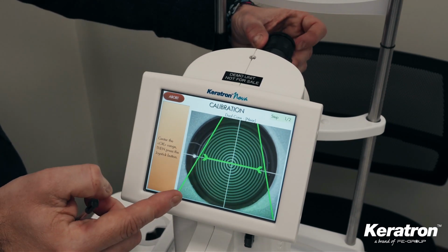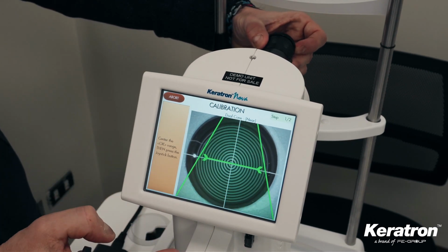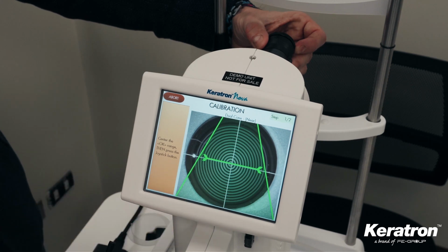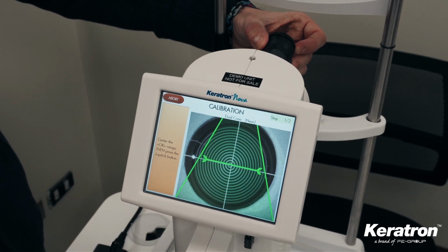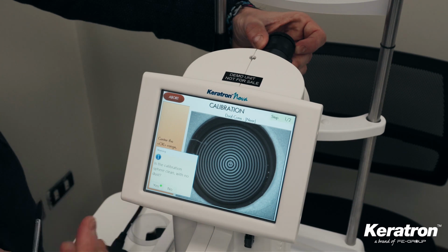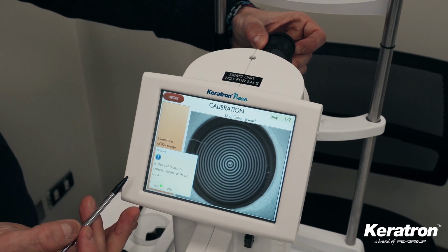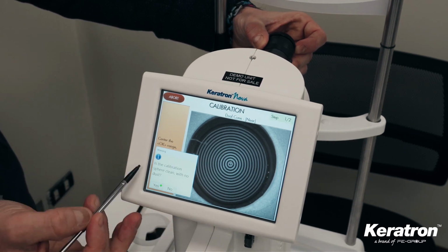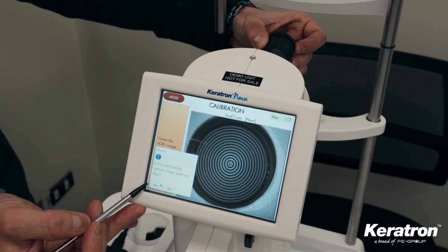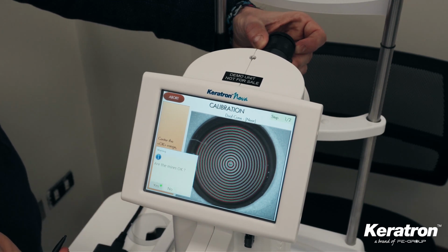and the reference cross for the position is completely green. Once this is done, we press the button. The machine's software will ask us if the calibration sphere has been cleaned before acquisition. We confirm this with yes and check whether the rings have been reconstructed correctly.